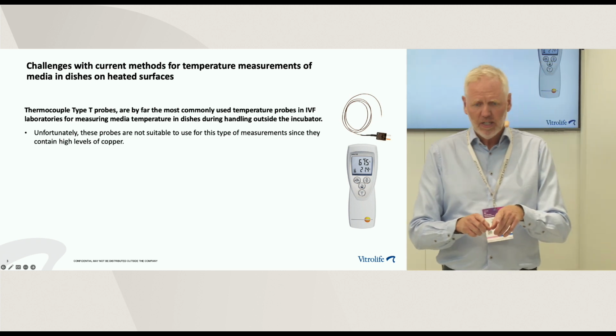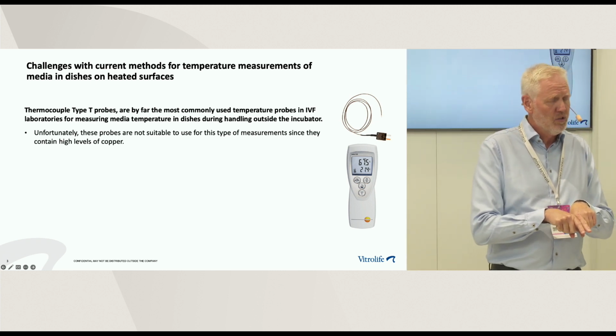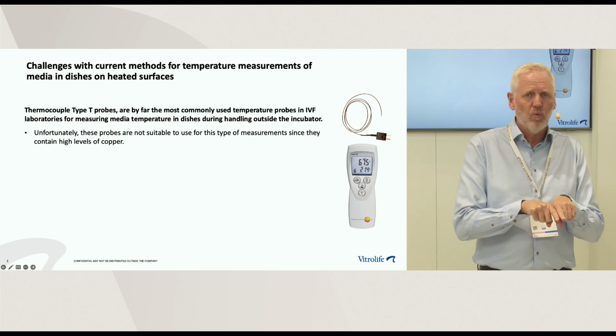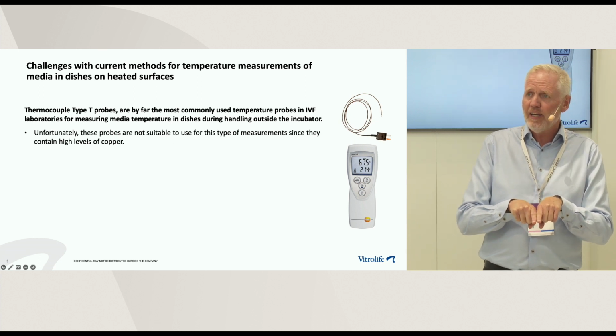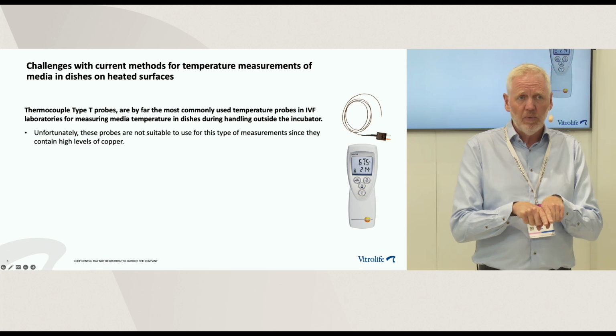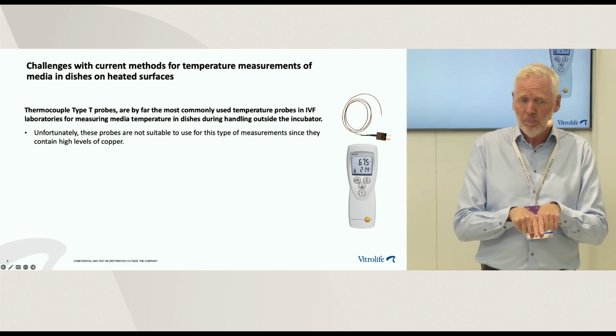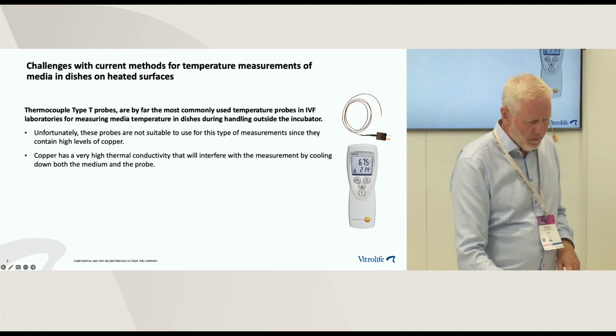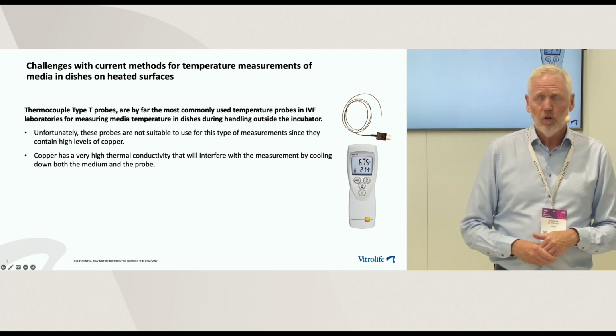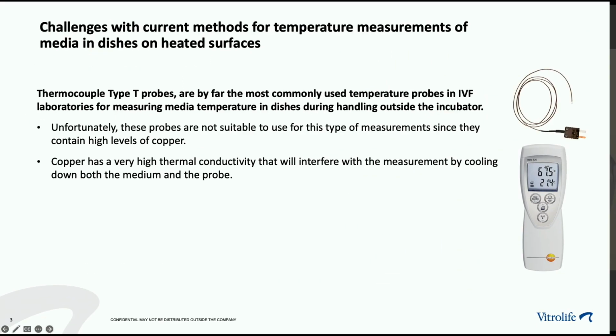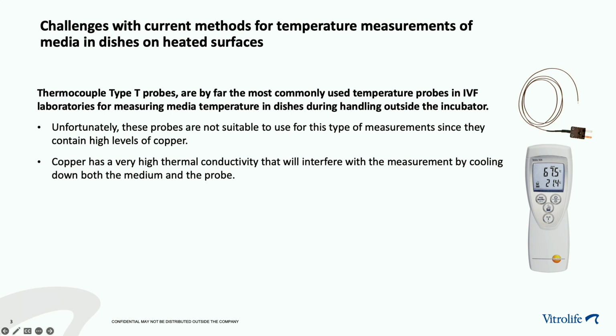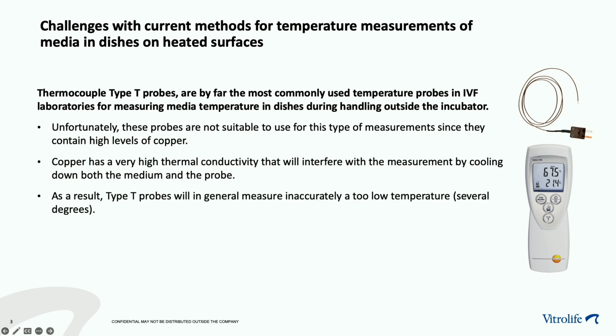A thermocouple type T is made of two wires. One wire is 100% copper, one wire is 55% copper in an alloy together with nickel, which means the probe is more or less made of copper. Copper has a very high thermal conductivity, and it will interfere with the measurement. It will cool down the media you measure, it will cool down the probe, and it will measure incorrectly. And it will measure incorrectly quite badly.